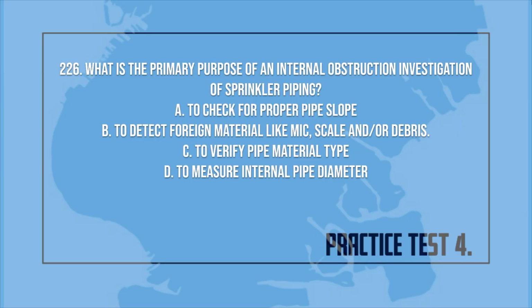226. What is the primary purpose of an internal obstruction investigation of sprinkler piping? A. To check for proper pipe slope. B. To detect foreign material like microbiologically influenced corrosion, scale, and/or debris. C. To verify pipe material type. D. To measure internal pipe diameter.